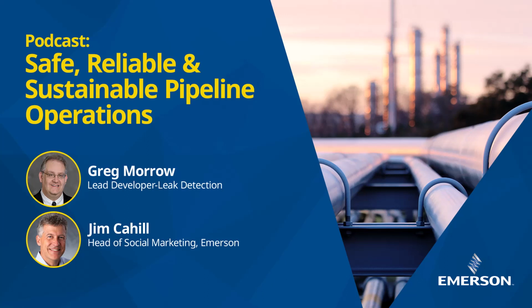So as a practice, a lot of tuning is actually understanding the instrumentation. That's both the instrument quality itself, as well as the SCADA data acquisition properties, like the report by exception that I mentioned, and also what part of the pipeline the instrument applies to. For example, if a pressure is upstream of pipeline equipment versus downstream of some pipeline equipment, like a set of valves or something like that, that can make a difference. And understanding that helps you get the model accuracy to match reality.